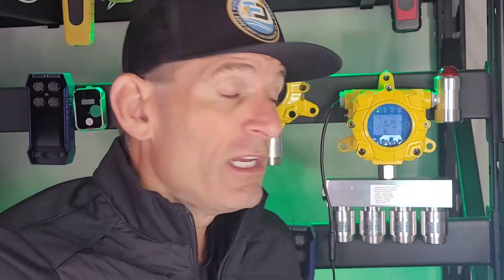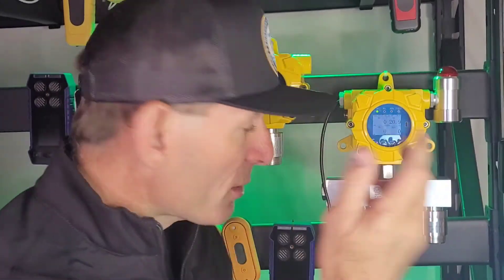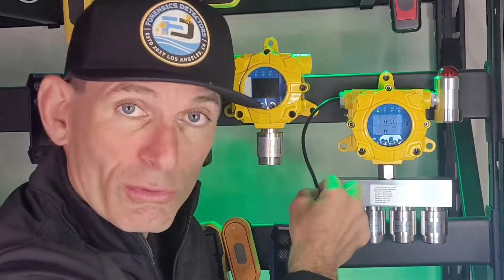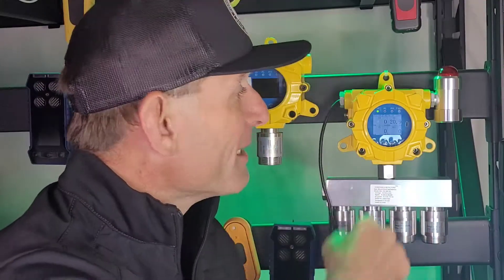The relays switch contact and non-contact, which can then trigger another buzzer or another alarm. You could go to a control panel, control a fan or a ventilation system. That's why we have the hex key — you can take the front cover off, or you could do some electrical plumbing onto the side here so it's fixed and you're not having temporary cables. You can fix it to your charger with a 24-volt line.